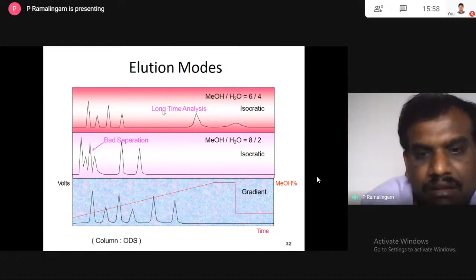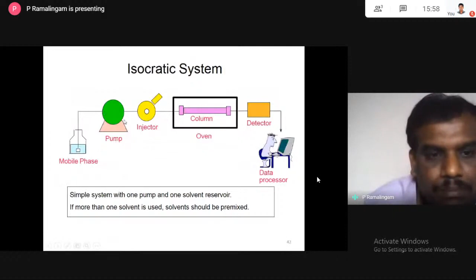One advantage of gradient elution is that you can separate many compounds with the expected resolution in a short analysis time. In the isocratic system, as I told you, only one pump will be there. We don't require 2 pumps here. In a high pressure gradient system, we require 3 or 4 pumps. In industry, you will have quaternary, meaning 4 pumps, and binary means 2 pumps. So you can set the solvent ratio in each pump accordingly. Each pump's solvent will mix and pass through the column. This high pressure gradient system has excellent gradient accuracy, and requires one pump per solvent.